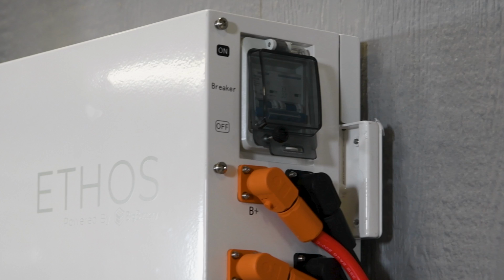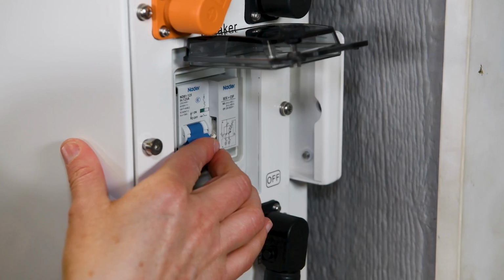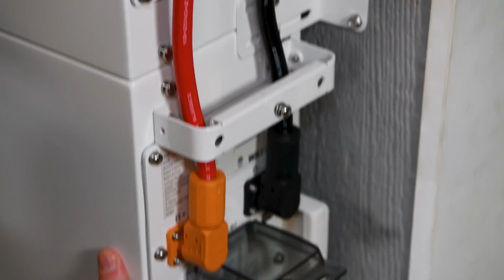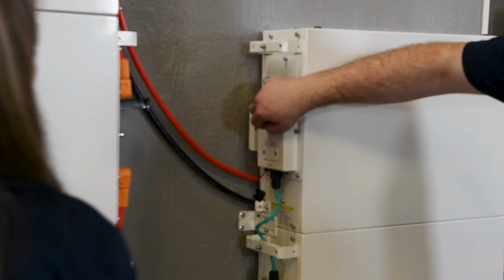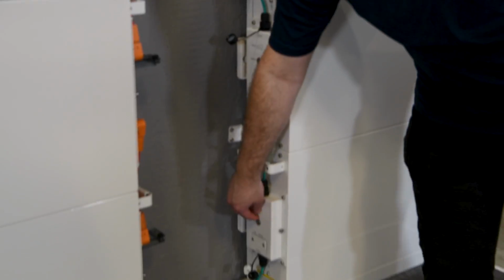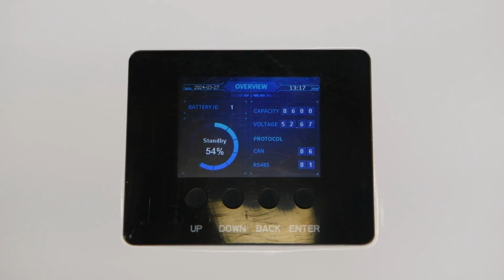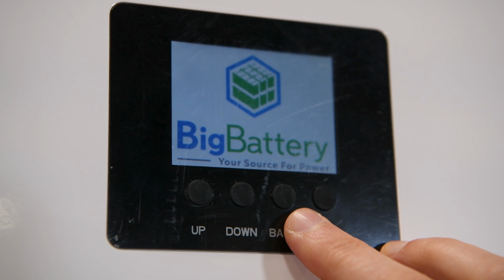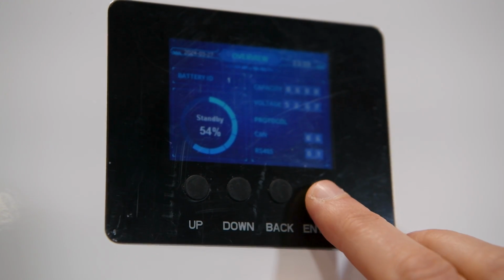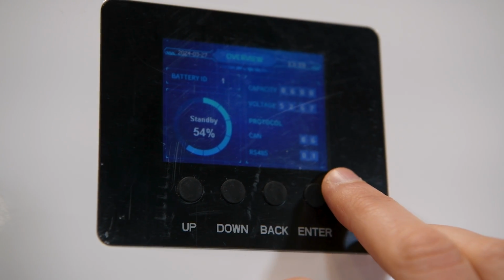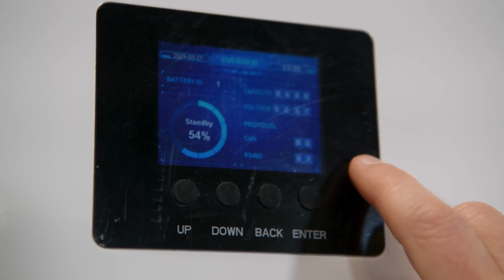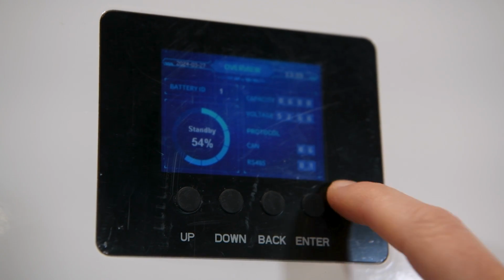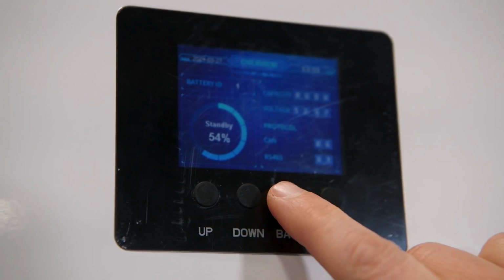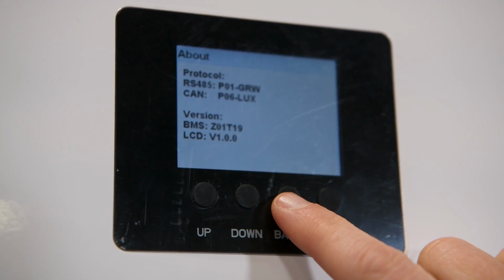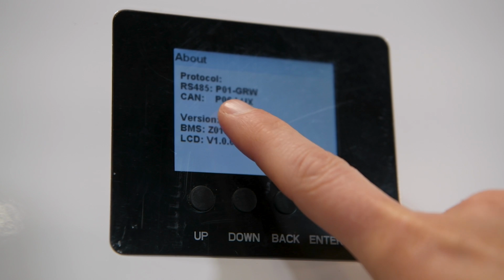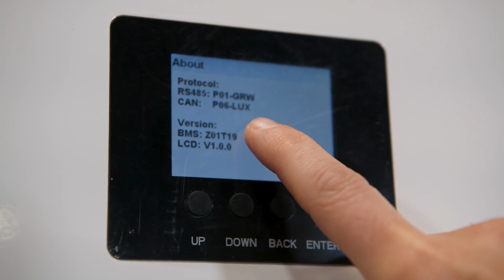To set up our communication protocols, the general startup procedure will be to turn on our battery breakers on our inverter, then we'll flip our battery breakers on our batteries, and then we'll push our power buttons on for our BMS, and then we'll start looking at our LCD screen. Start by pressing any button located under the LCD screen on the controller box to activate the screen. The initial splash screen displays several crucial details, including the date, time, battery ID, current status, capacity, voltage, and the communication protocols. We're about to configure these settings, and you'll notice these details update in real time.